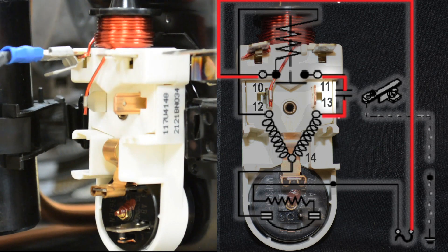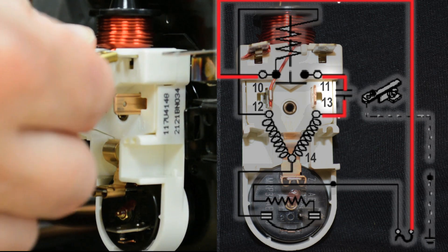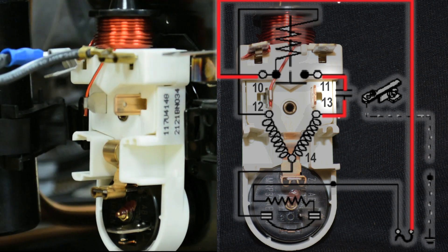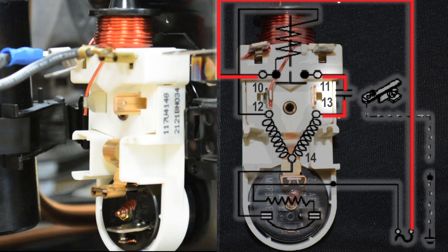Next we'll wire in the start capacitor in series between numbers 11 and 13 on the start relay, which will assist in starting the compressor energizing the start winding.